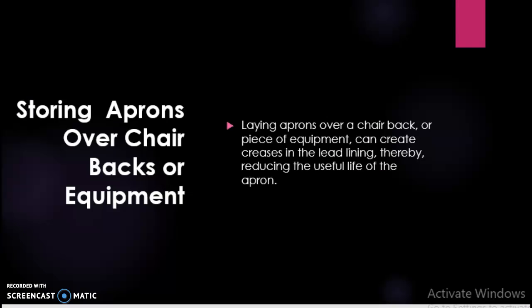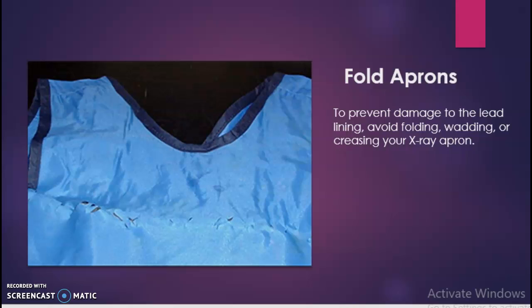And as mentioned earlier, never lay an apron over the back of a chair or a piece of equipment. It can create creases in the lead, thereby reducing the usefulness and life of the apron. And lastly, folding aprons. To prevent damage to the lead lining, avoid folding or creasing your apron. I know that we're all trying to store it, keep everything neat and clean, but folding a lead apron is not advised. All aprons need to be hung on approved apron hanging apparatuses.